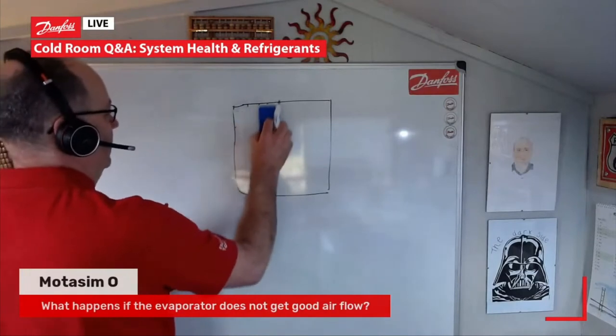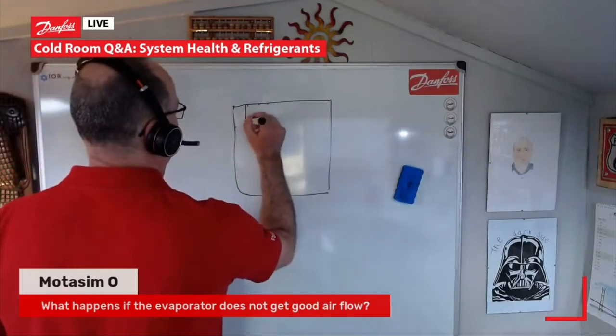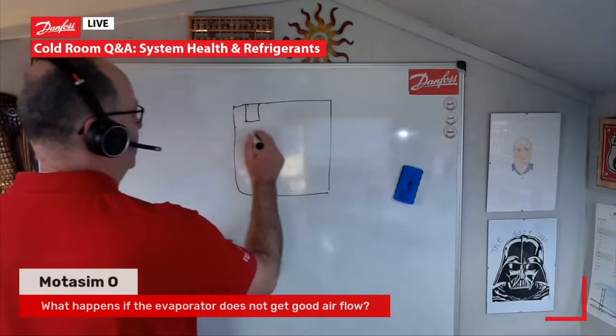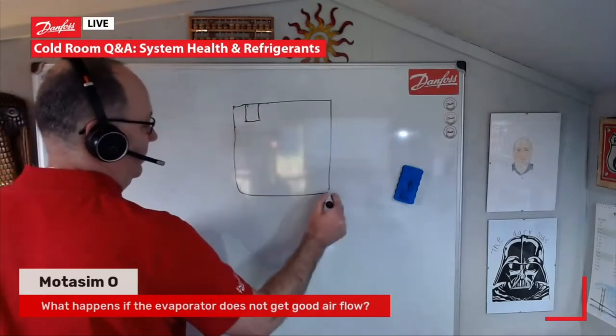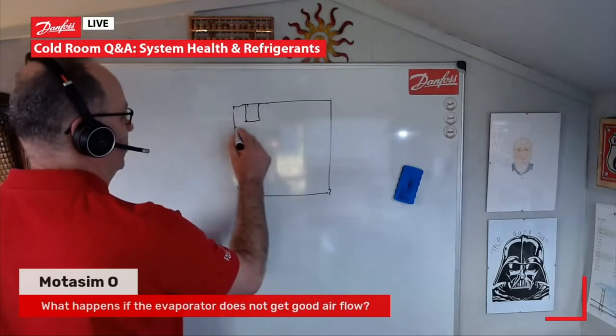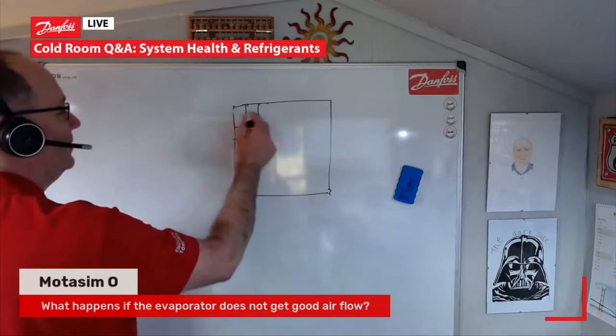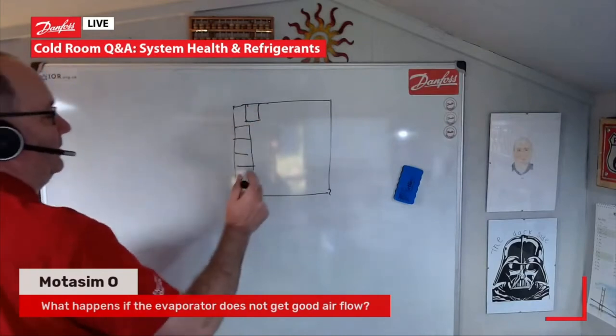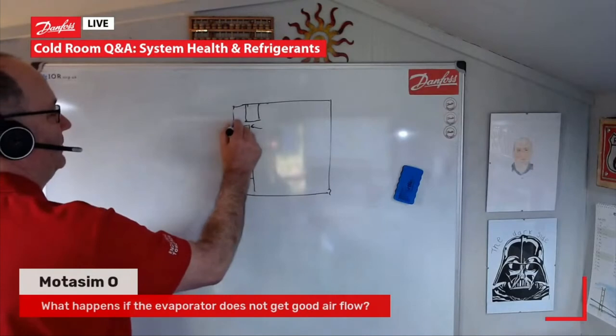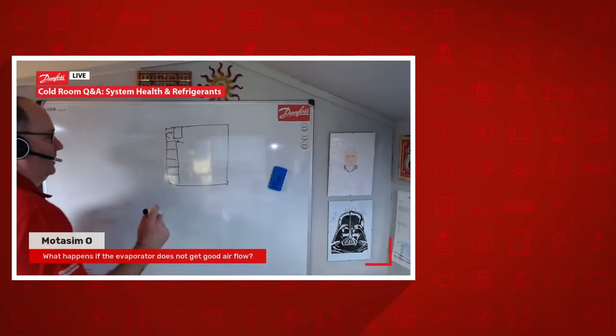Probably the biggest airflow issue in a cold room is when operators store product on pallets or racking around the evaporator, restricting airflow to the back of the coil. That's the most common problem I see when I'm on site with cold rooms. So yeah, the evaporator needs good airflow.